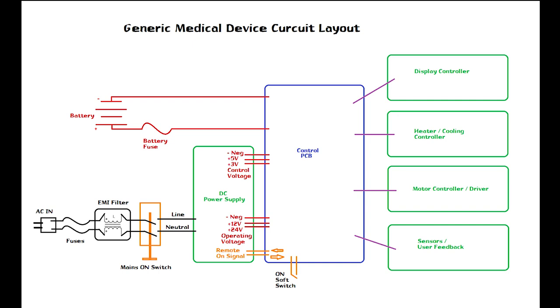So use this little flow chart to help you when you are trying to figure out how to troubleshoot a device. In other words, let's say that you have a problem with the device not turning on—very, very common problem. So let's say you check the AC first. You check the outlet obviously, because believe it or not, in hospitals they often pop circuit breakers. So you check the outlet to make sure that it's got power.